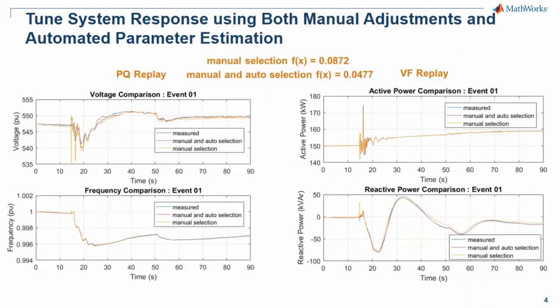Following manual adjustment and automated parameter sensitivity, automated parameter estimation can be applied to fine-tune the response. In this stage, we have observed that solution convergence, when you combine both PQ replay and VF replay, is more robust and accurate than separate PQ replay or VF replay. Parameter value ranges can be constrained in the automated parameter estimation task.